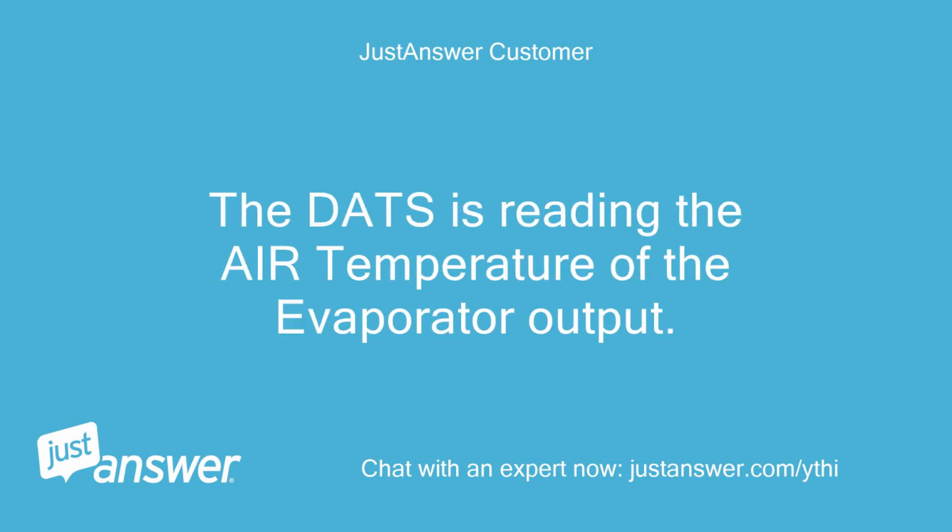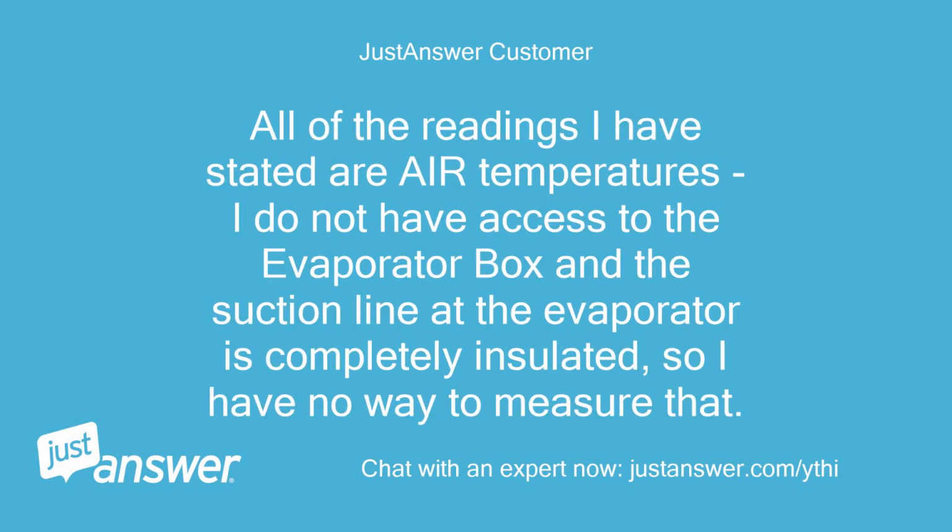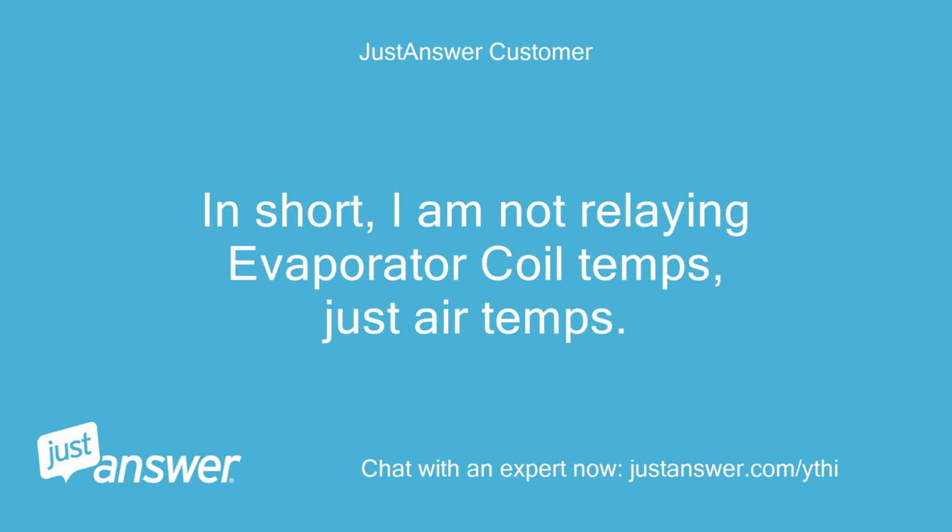The DATs is reading the air temperature of the evaporator output. It is mounted in the ductwork about a foot above the evaporator box. All of the readings I have stated are air temperatures. I do not have access to the evaporator box, and the suction line at the evaporator is completely insulated, so I have no way to measure that. In short, I am not relaying evaporator coil temps, just air temps.